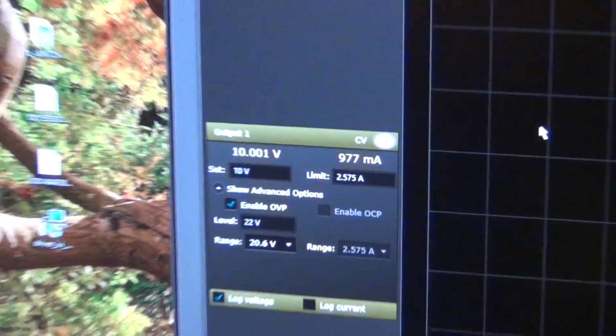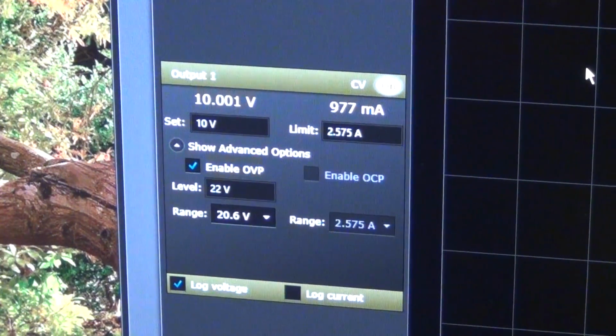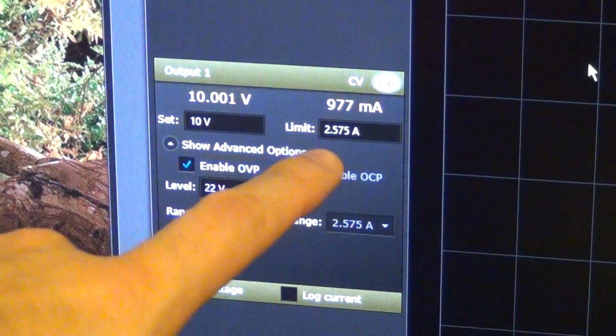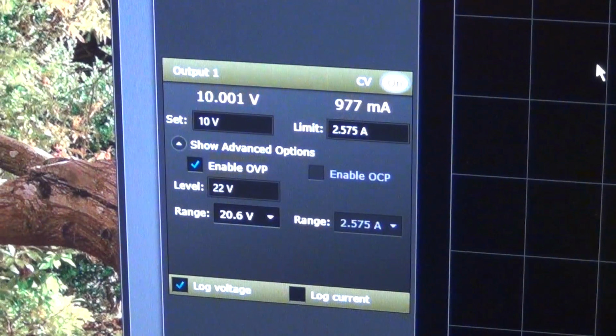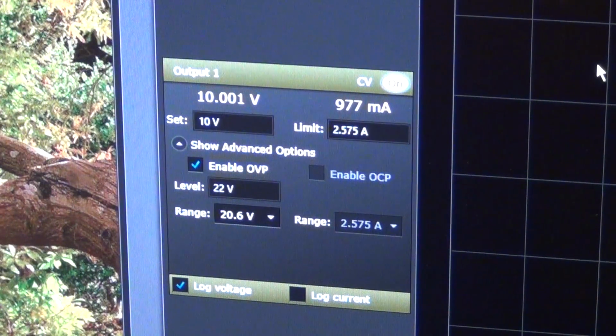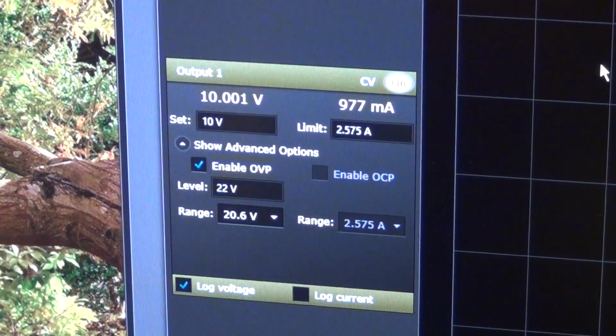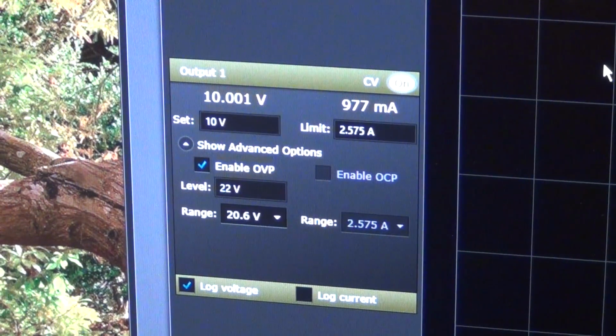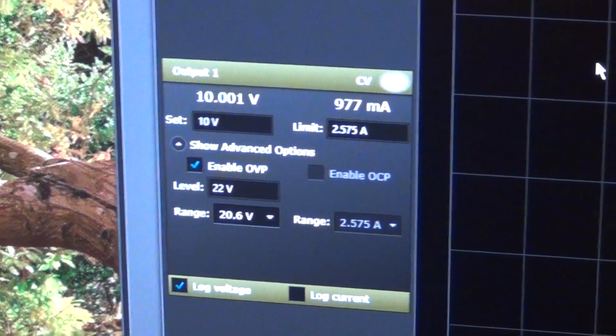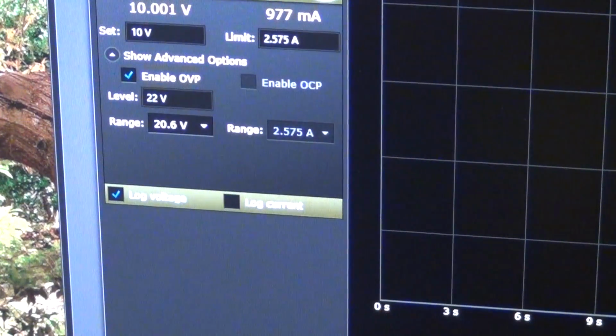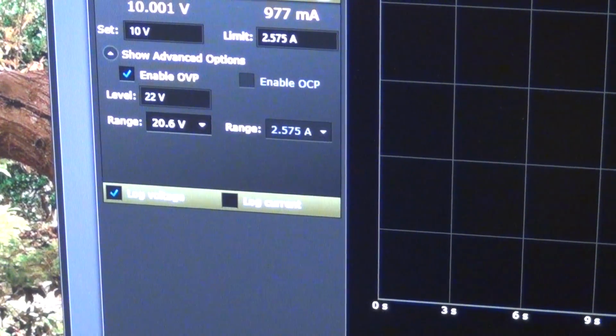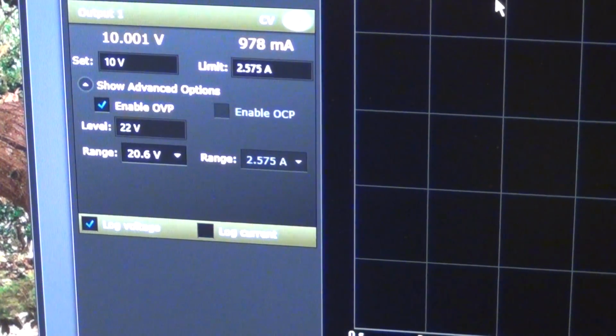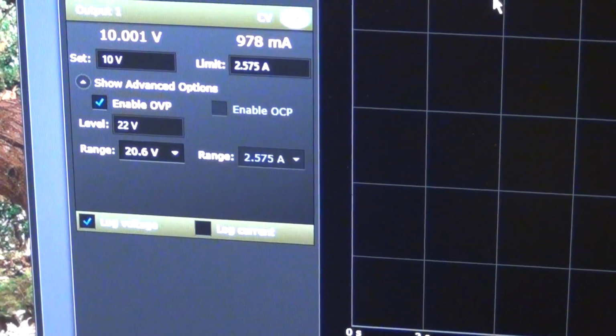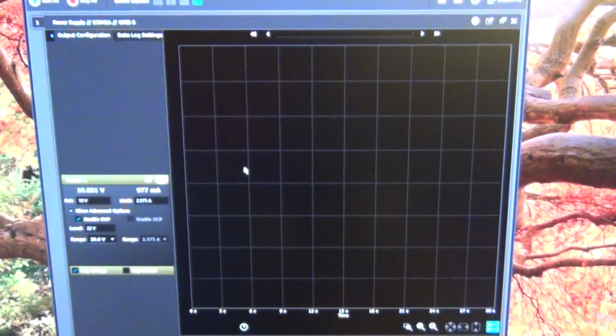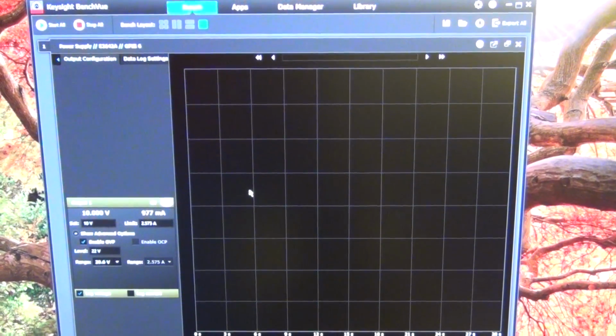So if I go back here, there we go. You can see that it is setting 10 volts. It's reading the voltage and the current correctly as well, 977. The Rigol is reading 976, and this is 10.001, and the Siglent is reading 9.998. So it looks very good. Again, the Siglent is expected to read lower because there is an IR drop through the connectors in the front. So it is fully consistent with each other. And this BenchVue software can do other things. You can plot and all that. We can look at that some other time.